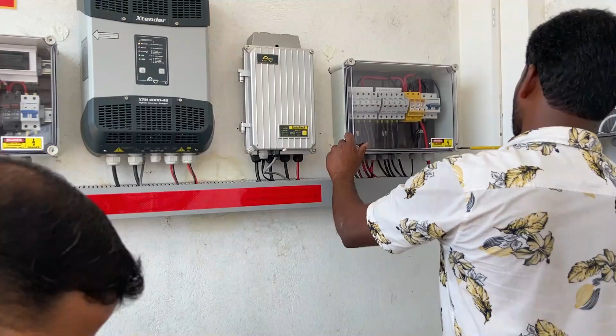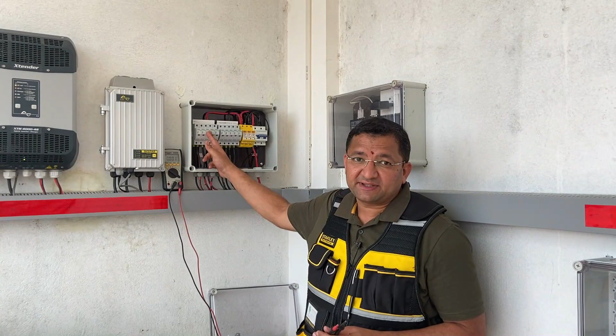Now we'll go in detail into this box and look at individual components. As shown, there are 10 panels of 480 watt peak each, with 2 panels connected in series forming 1 string, and a total of 5 strings. Since there are 5 strings, there are 5 fuses on the positive side and 5 fuses on the negative side.